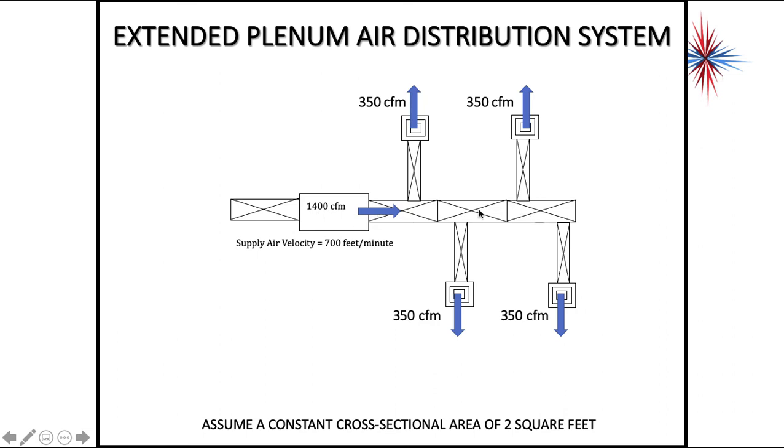So we know our supply quantity is 1,400 CFM. So we have to break this into 4, so each register is getting 350 CFM. 1,400 divided by 4 is 350. So it's a constant cross-sectional. That's an extended plenum system.